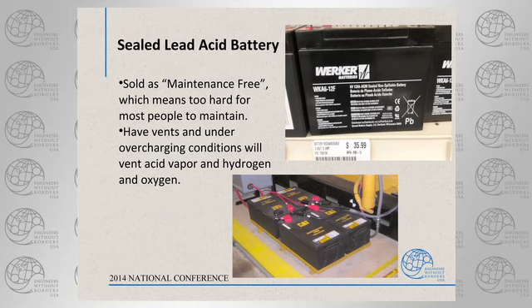So what does that mean? That means that you don't overcharge sealed lead acid batteries. So you have to be very cognizant of your charge controller settings and making sure that you're going to charge it a little differently in terms of voltages and times than you would a standard lead acid battery. The manufacturers are always going to provide you for their individual battery with the recommended charge levels. Pay attention to them, follow them.